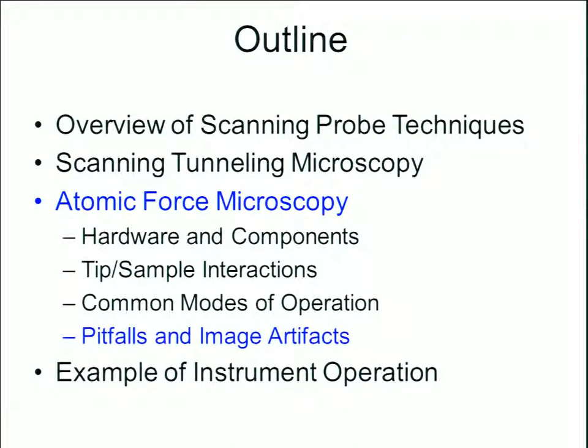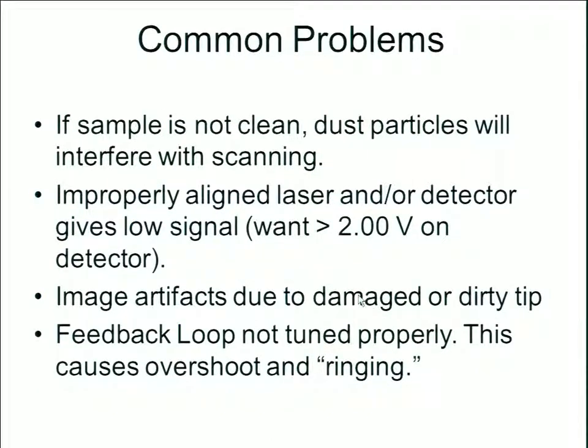Now, in our discussion of atomic force microscopy, we'll introduce a few pitfalls and image artifacts. If a sample is not clean, dust particles can and will interfere with scanning. An improperly aligned laser or detector will give a low signal; if the signal is not great enough, the signal-to-noise ratio will be insufficient, giving unreliable data with too much background noise. We can also accumulate many types of image artifacts due to a damaged or even slightly contaminated tip.